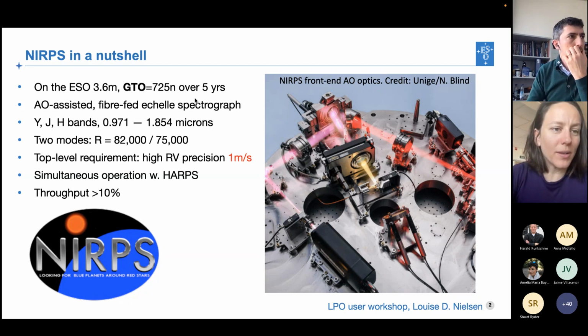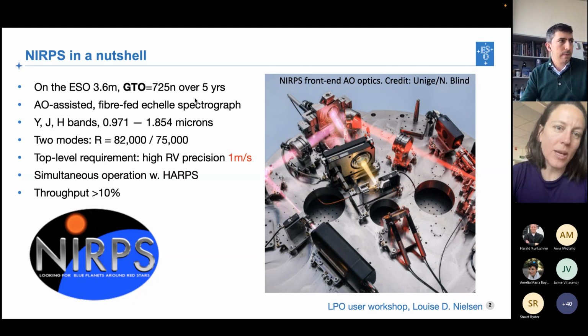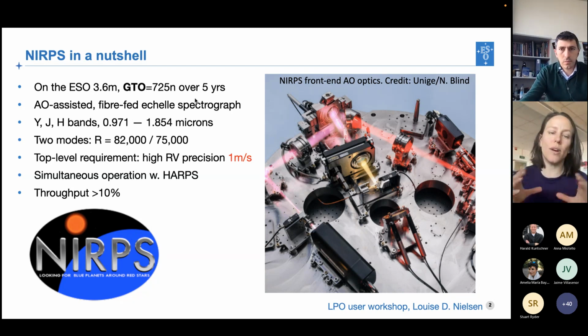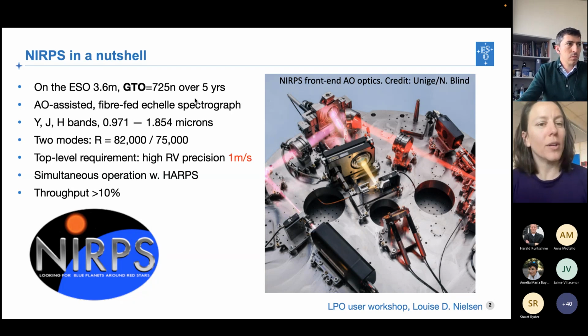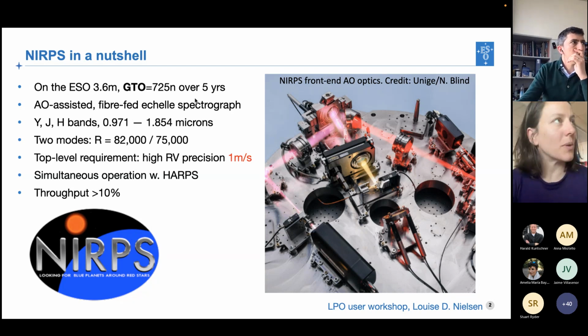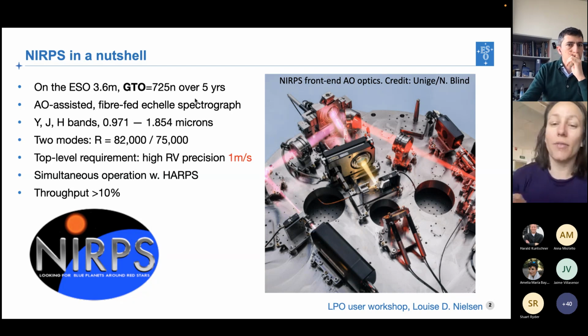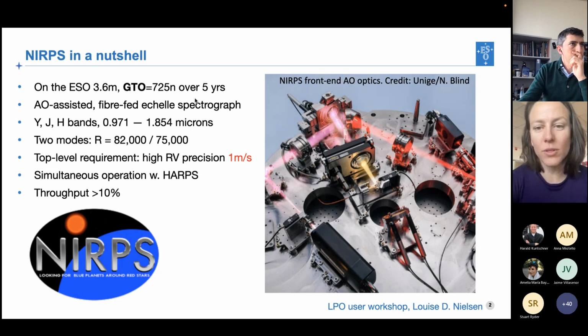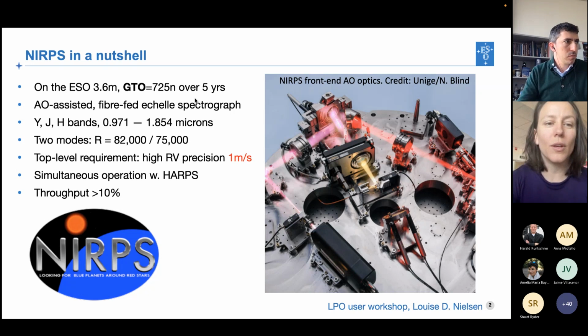What's very new about NIRPS is that it's AO assisted, meaning we're using an AO system to feed our very small fiber, because in the near-infrared you either need a very large spectrograph or a very small fiber to feed your spectrograph to obtain a high resolution. The spectrograph operates in Y, J, and H band, and we have 2 different modes using 2 different size fibers that give 2 different resolutions. And the numbers I have on the screen here, 82,000 and 75,000, those are the most, let's say, updated numbers on the actual resolution that we are achieving in the instrument.